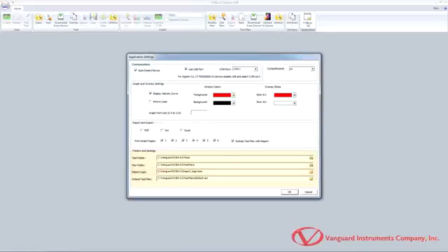The VCBA S2 software can use a default test plan for performing tests. The default test plan defines color settings for graph elements, default values for analysis points, and other default testing parameters. You can set a default test plan in the Default Test Plan field. Click on the OK button when you've made any necessary changes to the application settings.